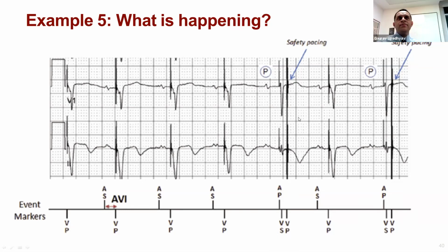Terrific. And I think related to that is you also want to investigate why this wasn't set. Absolutely. Yeah, just to make sure there's nothing else going on. But you will see the safety pacing if you look for it. And it's usually PVCs that are sensed where you see a pacing deflection right after, for a patient who had an unfortunately timed PVC.